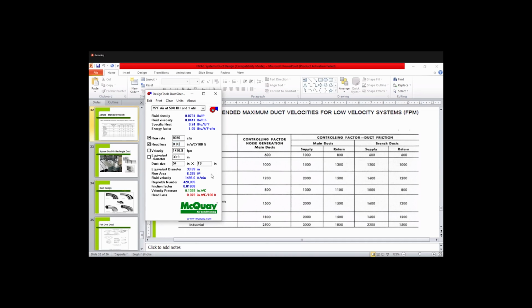Okay, and one more thing also, that the ratio of the width and the height should be 4:1. Okay, it should not exceed that. 4:1 means if the width is 200, then the height should be 50. It should not be like the width is 600 and height is 250. So the ratio increases, no? So it should be within 4:1.